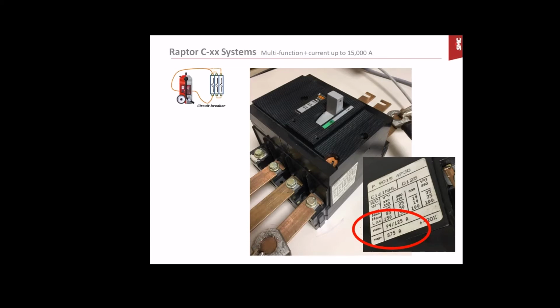And there is also a magnetic element which is set up to 875 amperes. You can see there it has a tolerance plus minus 20%, which means that any current above this limit will produce an immediate trip. It will be considered as short circuit or very high dangerous current, so the circuit breaker should trip immediately. And this is what we are going to test: the thermal and the magnetic protection characteristics on this breaker.